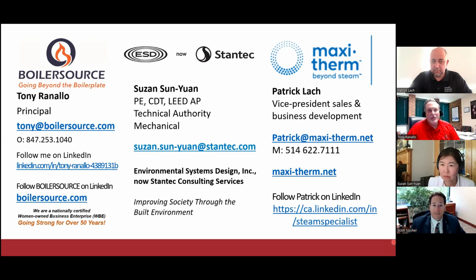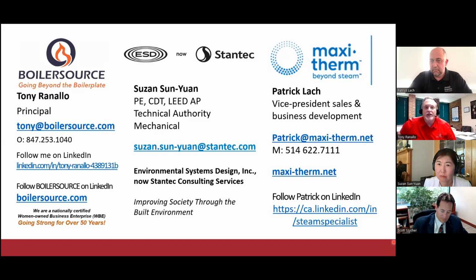One of the biggest things that we're seeing today, and this applies across the board for anything, is right sizing equipment. But one of the biggest things that's happened over the last 10 years in the boiler industry is getting burners that have high turndown. So we push and we promote high turndown, low excess air burners. So we make the burner burn as efficiently as we can.